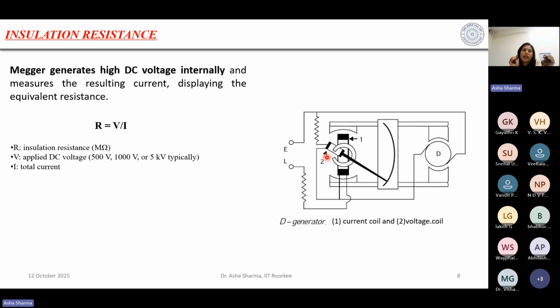At balance, the deflecting torque must equal the controlling torque, and when TD is proportional to TC, we say V is proportional to I. So R equals V by I, and in this way we can measure the insulation resistance. This is the whole principle of the megger.